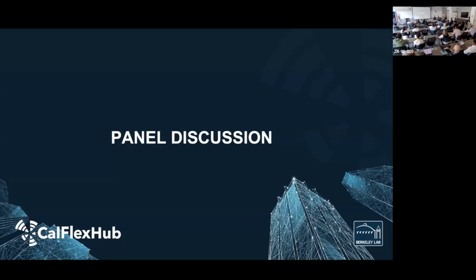I can try to reply. We definitely considered it, and you're right, unfortunately we did not run a specific study on that. But in a previous study, someone tested MPC using an energy minimization objective, and the results were pretty similar. It really depends on the round trip efficiency of your flexibility. In our case, because the building is pretty new and fairly well insulated, and we were activating the thermal core, the concrete core of the building, that thermal shift did not affect the energy consumption much. I didn't show it in the slides, but the MPC still uses less energy, especially in winter and fall, than the baseline. Usually you start from a baseline controller, not necessarily an optimizing MPC, so sure there's a bit of trade-off, but given that starting point, on average the MPC still does a better job, even with a different objective.